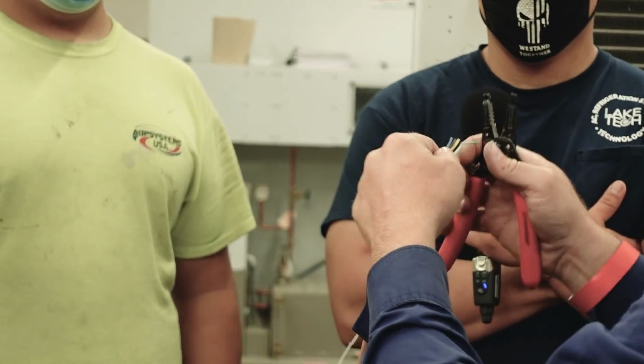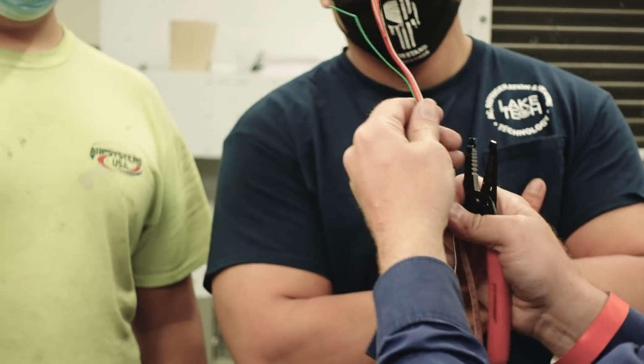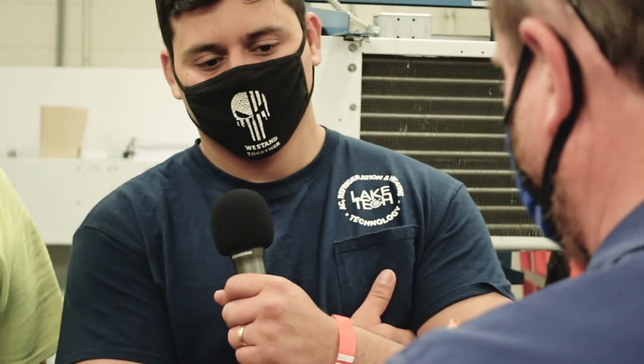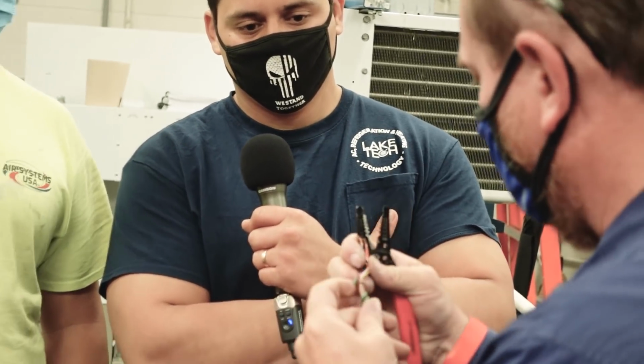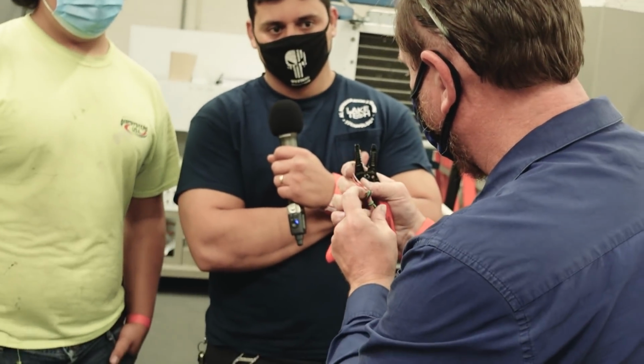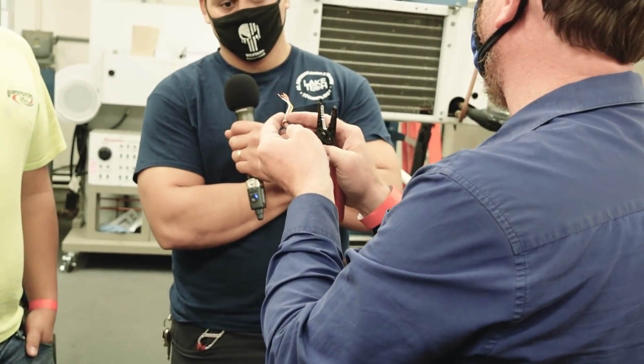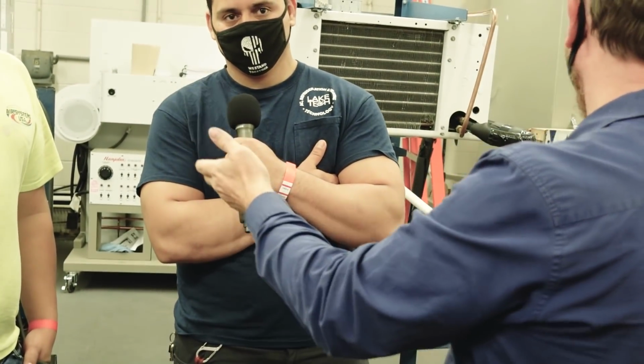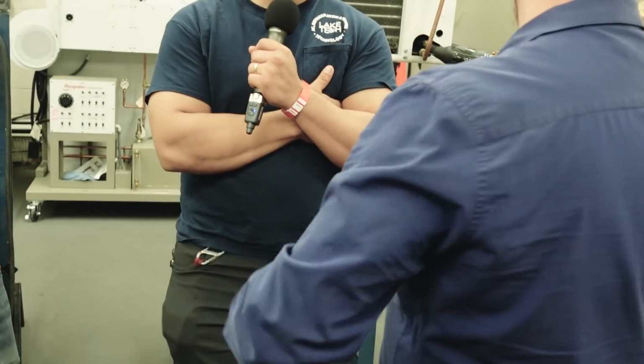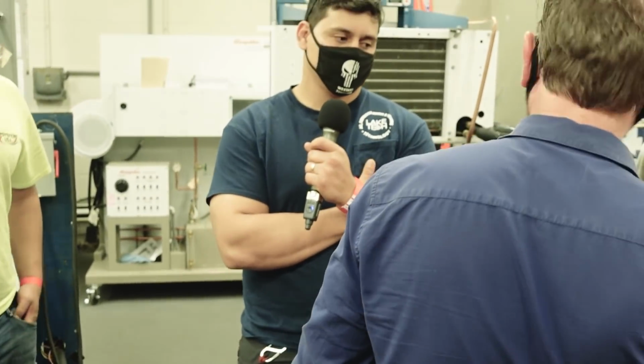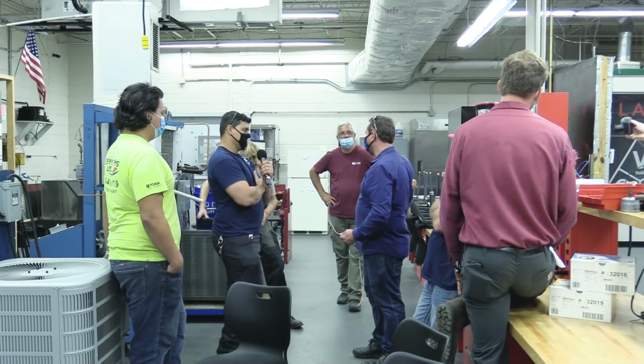Now I can cut all these nicks off and strip them individually. But that's a huge issue where people do that right there. They take and they cut this and do it like right here. Nope, that was actually done fairly nice. That was good. But they'll short right there. And the next thing you'll have is a contactor that's shorted out. The coil, like we had this one that was burned up, it burns out, the resistance is too low.